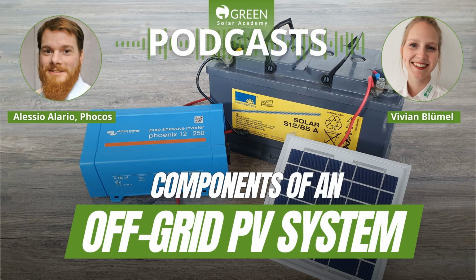That's good information, I think, especially for off-grid systems that are installed in very remote areas. You don't want to go back to have your components fixed all the time. So if it's long-lasting, you install it once and then it just runs. And also PWM tends to perform better for many years at hotter temperatures. Okay, so for deserts or... Exactly, yeah. The high temperatures, extremely high temperatures, I'm talking like 40, 45 degrees centigrade and more, tend to make the electrolytic capacitors in inverters and MPPT charge controllers age more quickly. And PWM charge controllers just don't have those, or certainly not as many. And so they will tend to be a little bit more robust.